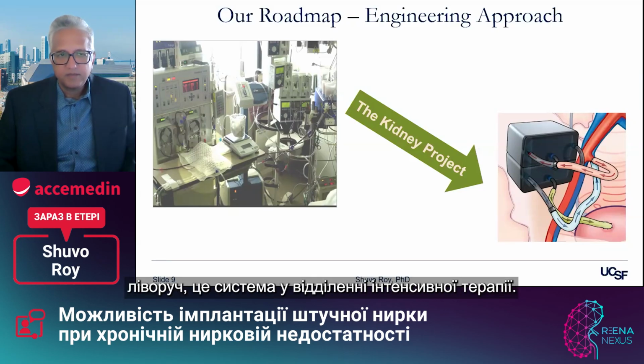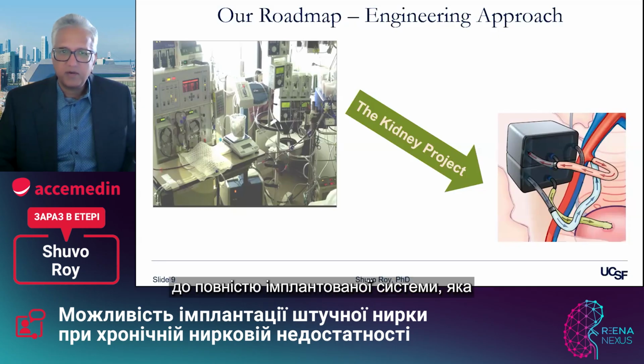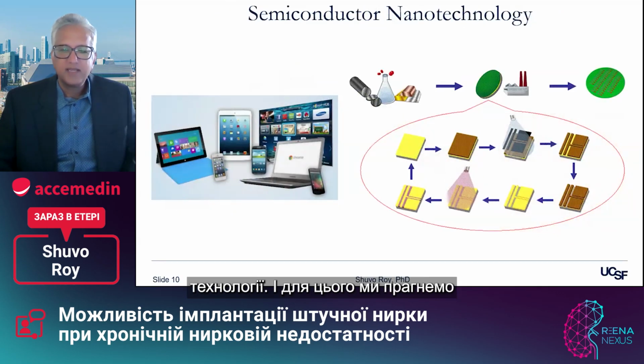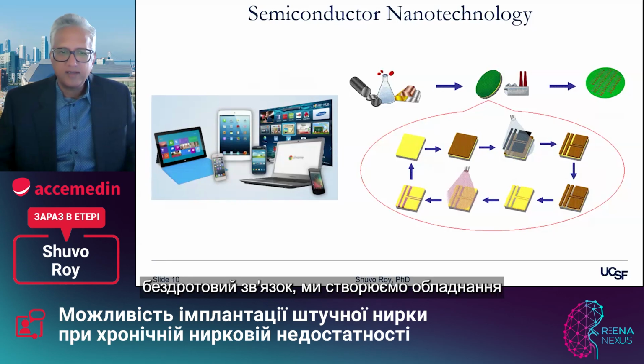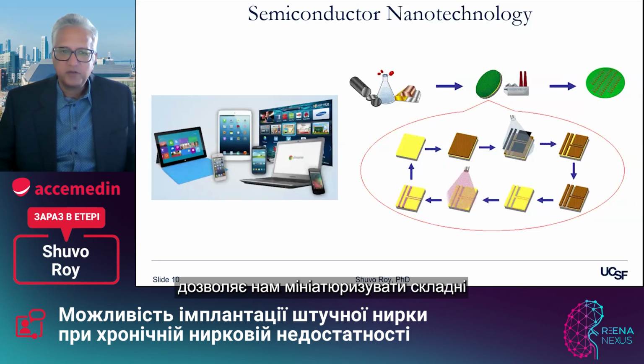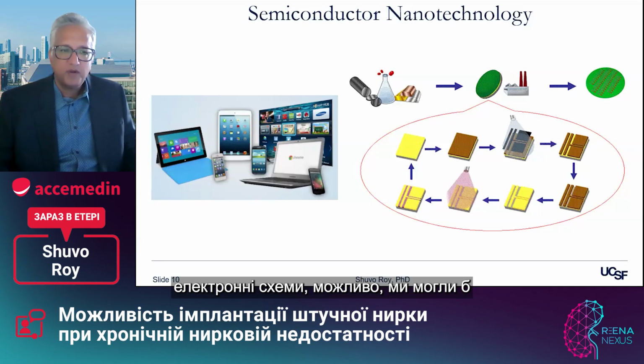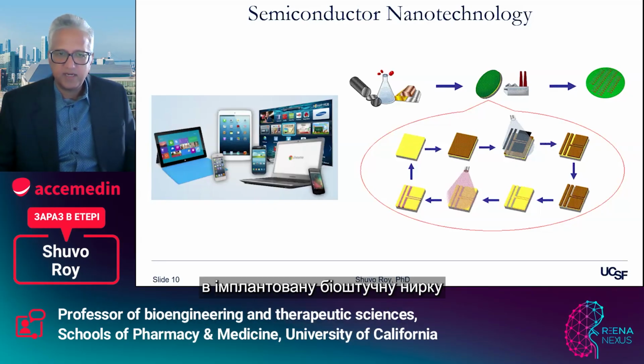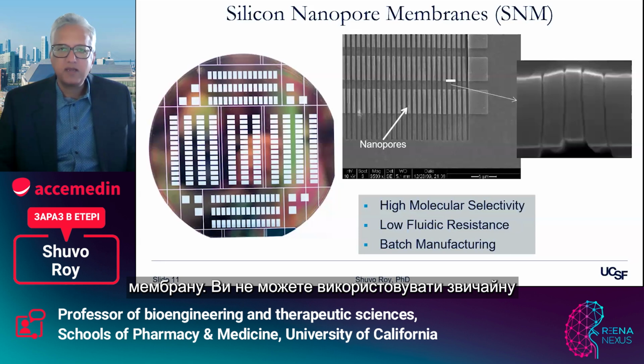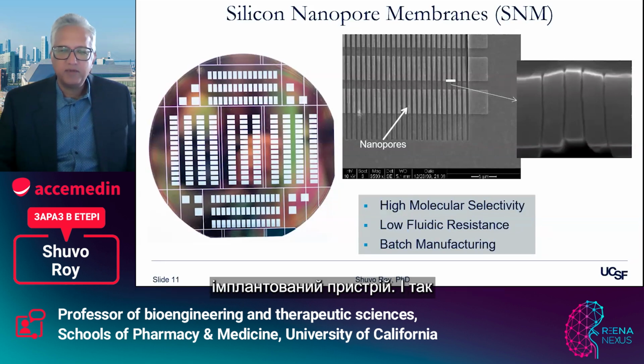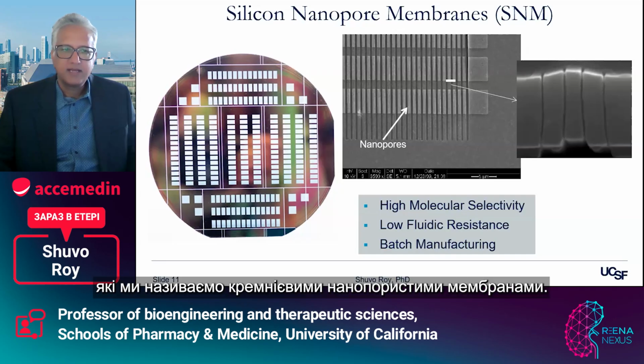So to move from the left, which is the system in the ICU, to a totally implanted system that operates autonomously in the body, we have to leverage state-of-the-art technology. And for this, we look towards semiconductor nanotechnology, the same technology that's allowing me to communicate with you: electronics, wireless. We're making the hardware for computer chips. So by using the technology for computer chips that allows us to miniaturize sophisticated electronic circuitry, perhaps we could miniaturize the renal assist device into an implantable bioartificial kidney. And the fundamental breakthrough to make that happen is a next generation membrane. You cannot use the conventional dialyzer membranes for an implantable device. And so we ended up developing a new membrane technology using semiconductor silicon that we call silicon nanopore membranes.